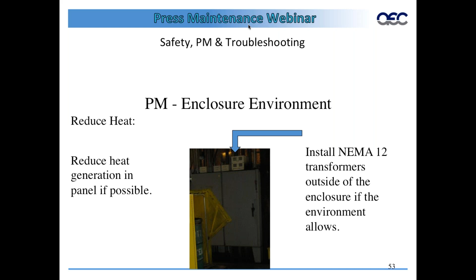All panels should have some way to remove heat. One simple way is to allow natural convection, letting the heat rise and leave the panel, but it needs to be set up the correct way. I've even seen electrical panels and controls made by professionals that had it wired wrong. The proper way is for air to flow in through the bottom on one side and out the top on the other, since heat rises. You want the cooler air entering at the bottom, flowing across all the components, and then exiting at the top.